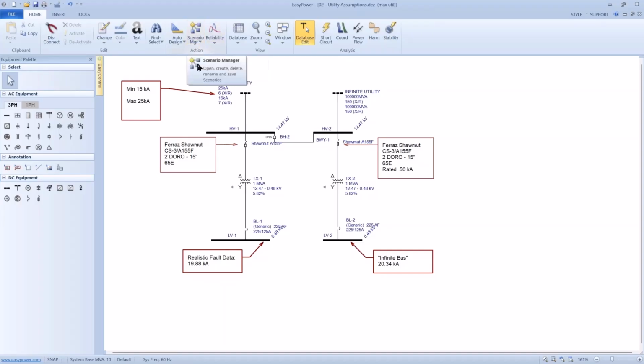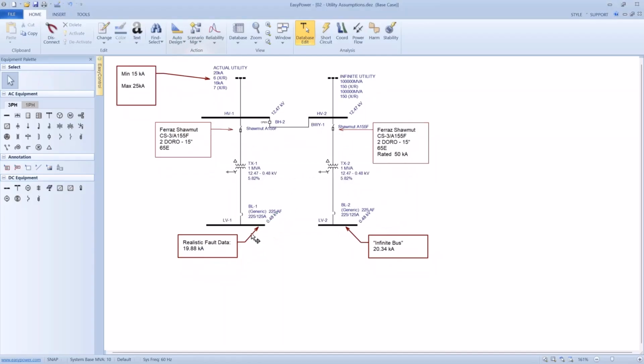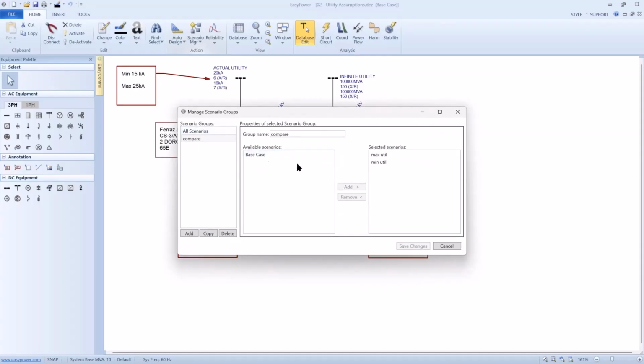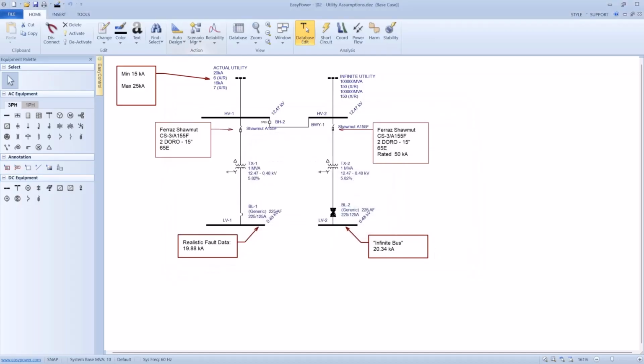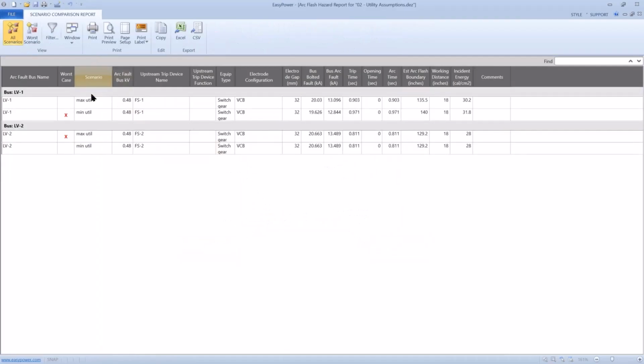And now I want to see what the difference is at this bus in terms of incident energy. And to do that, I use this. I'm going to go back to my base case. I'm not going to change anything. Select that bus that I'm concerned about. I'm going to go into Scenario Manager, create a comparison report for arc flash, and see which is worse. And so to do that, I've created a report that has the max utility and the minimum utility. And that's what I'm going to exercise for this single bus, LV1. So LV1, the worst case is the minimum utility current, because it's almost 2 calories worse than the maximum utility.